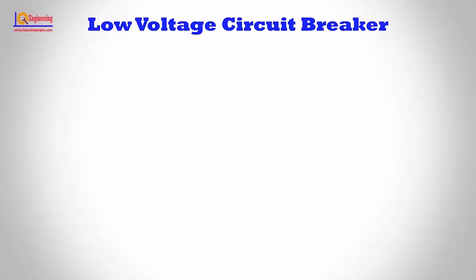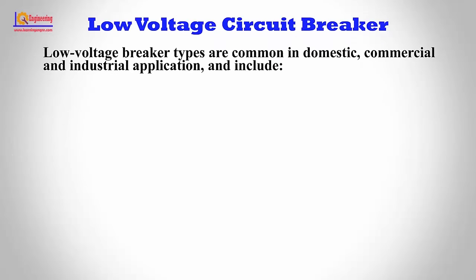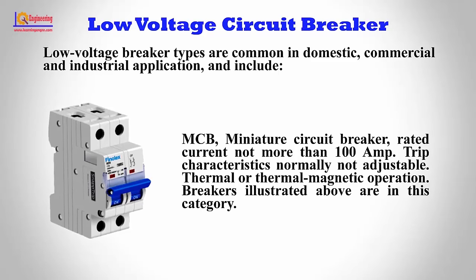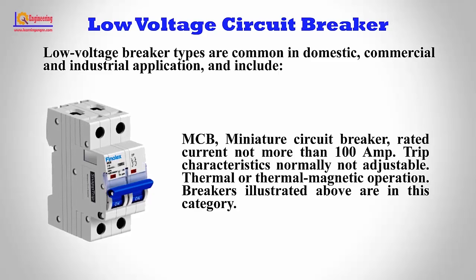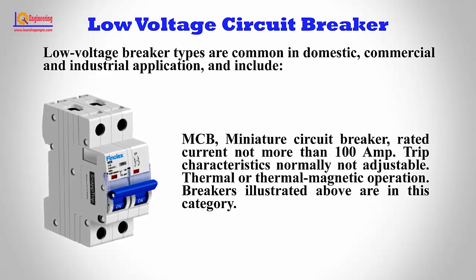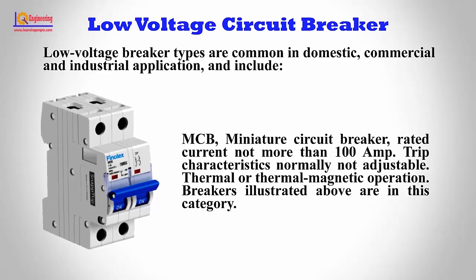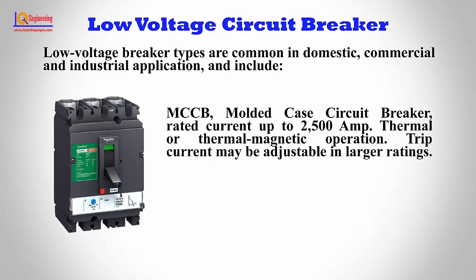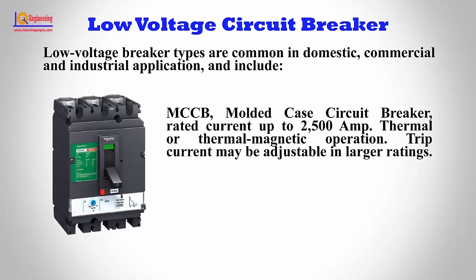Low Voltage Circuit Breakers are common in domestic, commercial, and industrial applications and include MCB (Miniature Circuit Breaker), rated current not more than 100 A, with trip characteristics normally not adjustable, using thermal or thermal-magnetic operation. MCCB (Molded Case Circuit Breaker) is rated current up to 2500 A with thermal or thermal-magnetic operation; trip current may be adjustable in larger ratings.